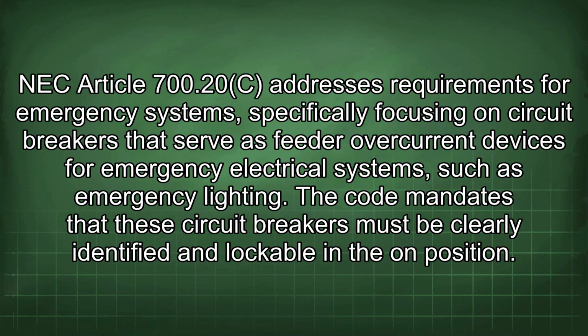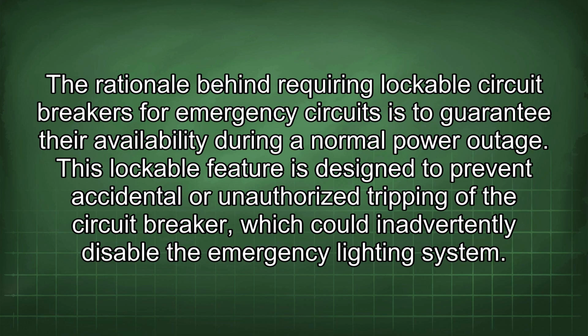NEC Article 700.20(c) addresses requirements for emergency systems, specifically focusing on circuit breakers that serve as feeder overcurrent devices for emergency electrical systems such as emergency lighting. The code mandates that these circuit breakers must be clearly identified and lockable in the on position. The rationale behind requiring lockable circuit breakers for emergency circuits is to guarantee their availability during a normal power outage.